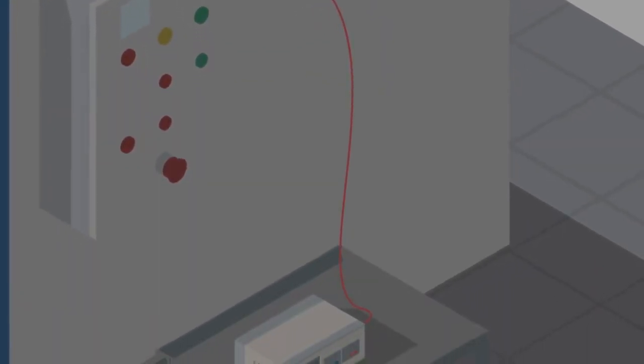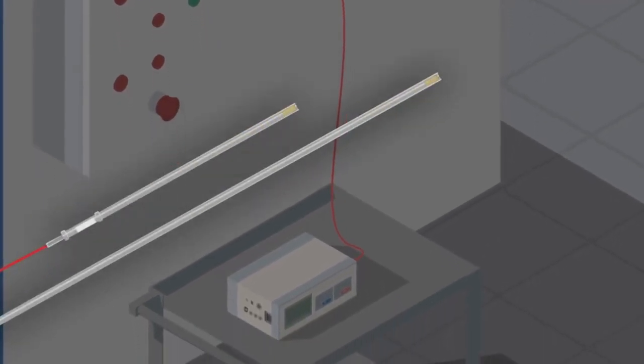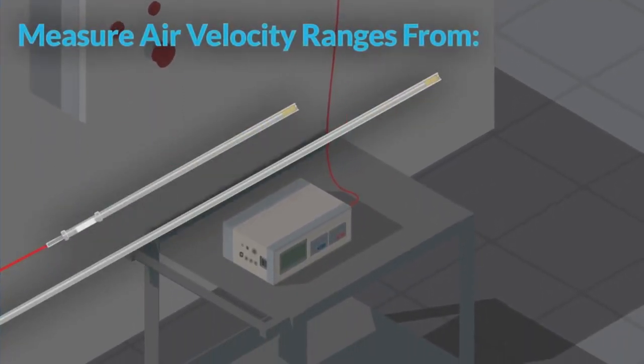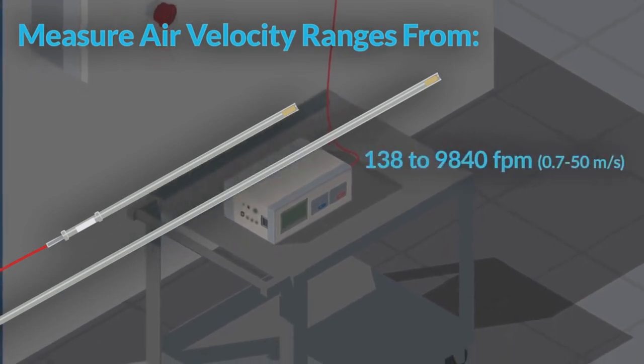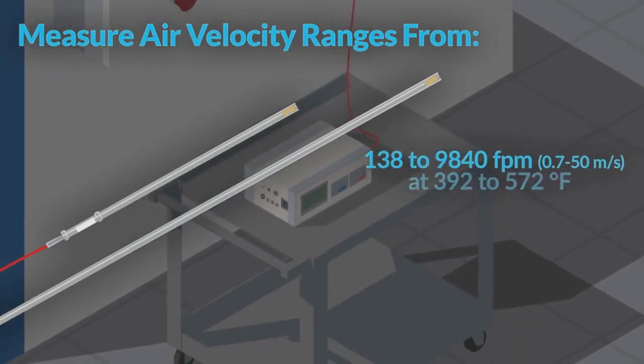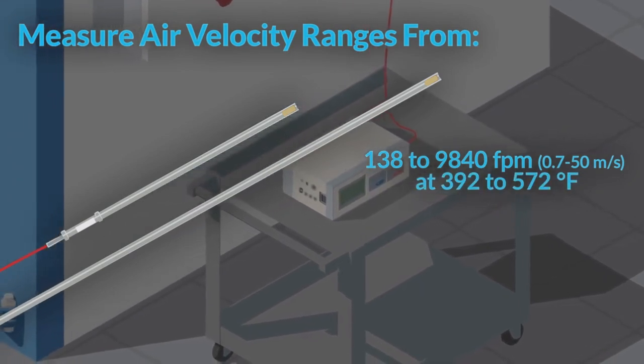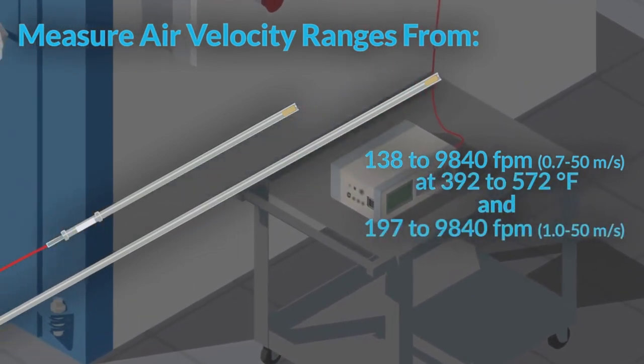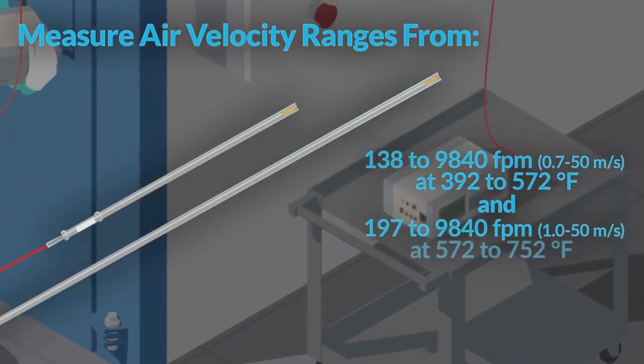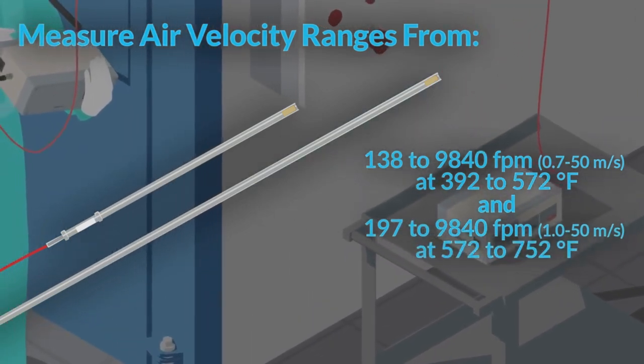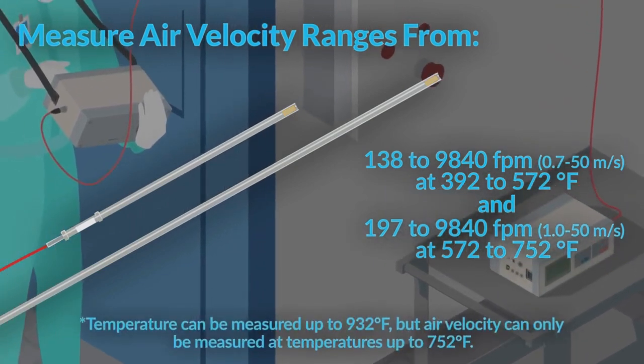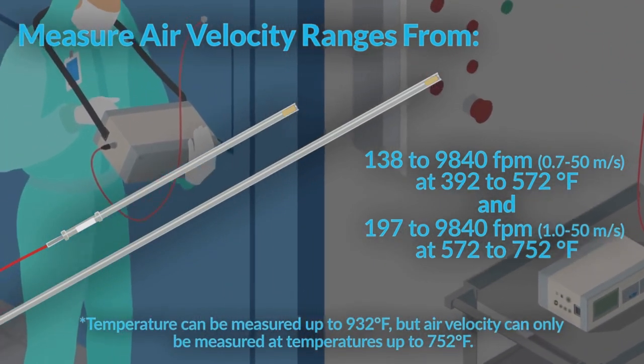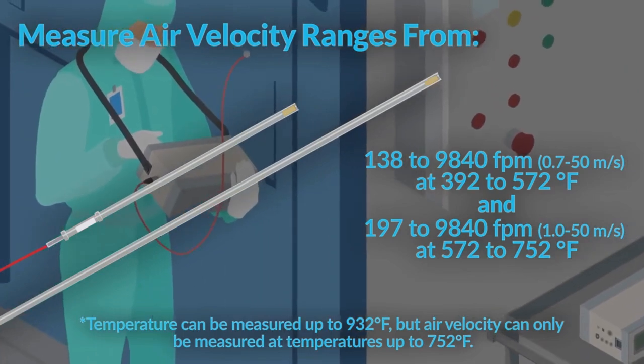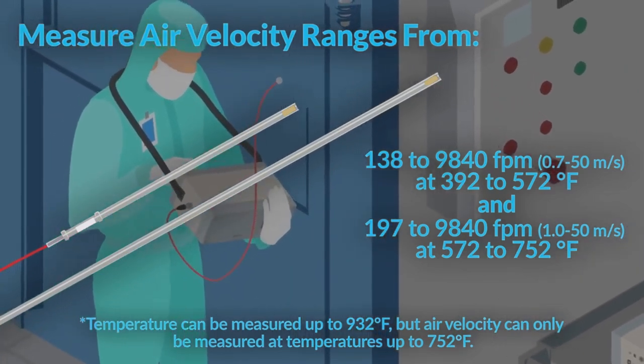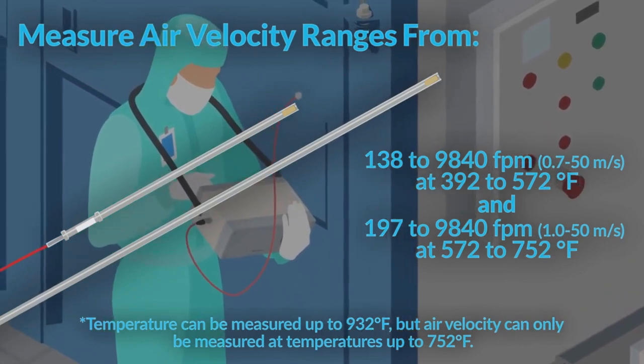If you're testing an environment that ranges 212 to 752 degrees Fahrenheit, use probe model 0204 or 0205. They can measure air velocity ranges from 138 to 9,840 feet per minute at 392 to 572 degrees Fahrenheit, and 197 to 9,840 feet per minute at 572 to 752 degrees Fahrenheit. Something to note is that temperature can be measured up to 932 degrees Fahrenheit with the 0204 and 0205, but air velocity can only be measured at temperatures up to 752 degrees Fahrenheit.